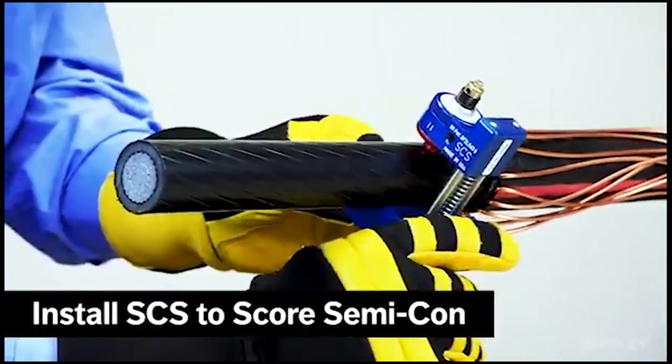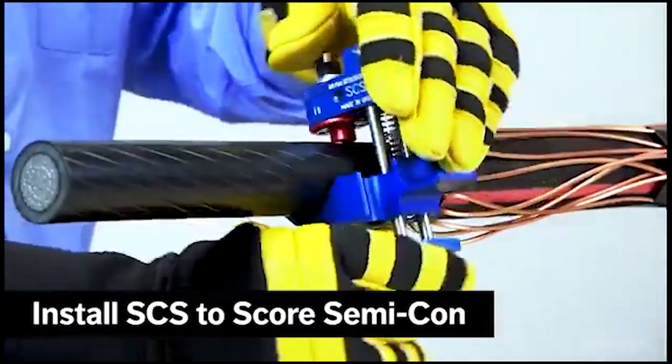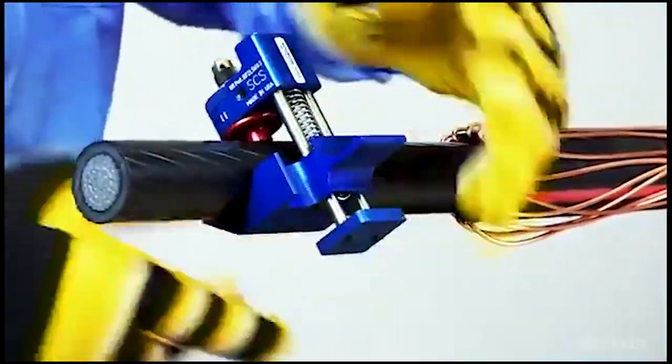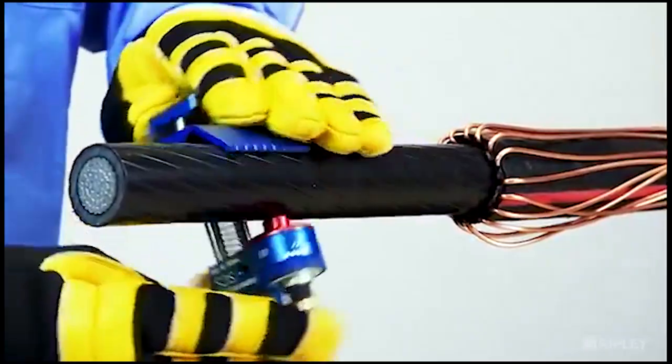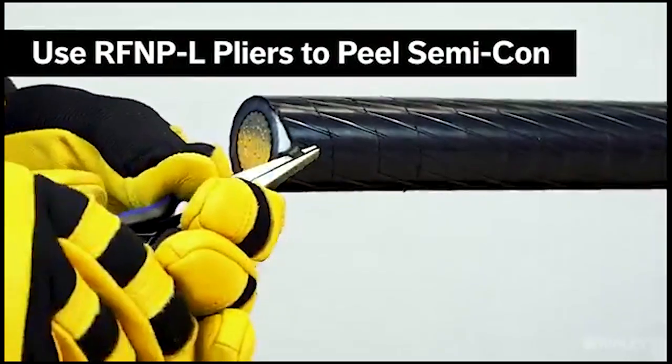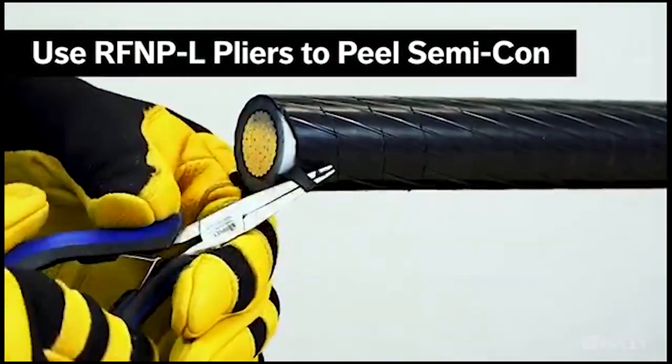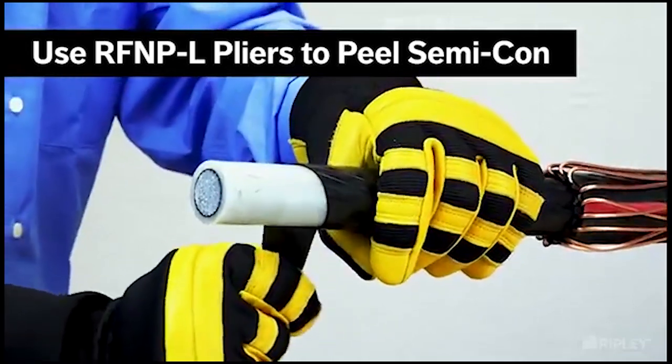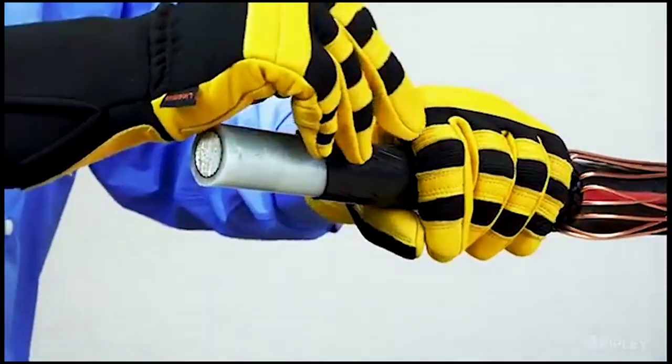Install a semi-con scoring tool such as the SCS onto the cable to score the semi-con layer. Use a pair of flat nose pliers such as the RFNP-L to begin peeling away the semi-con and exposing the insulation.